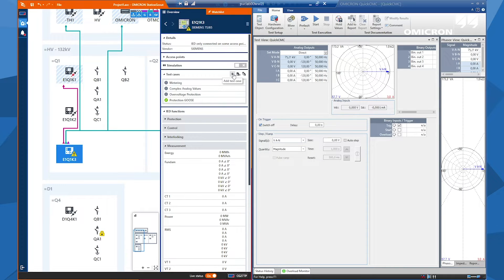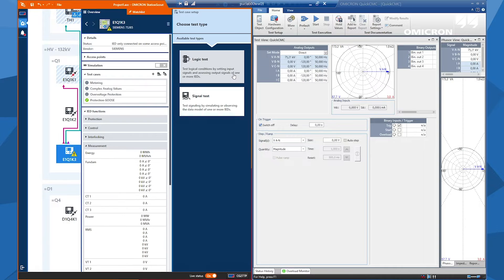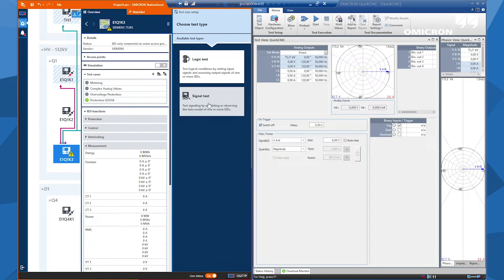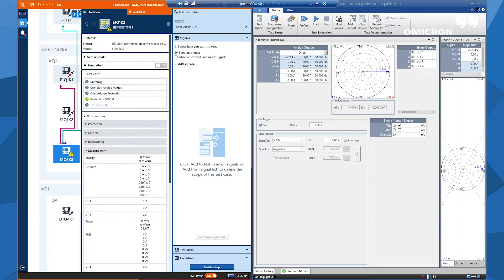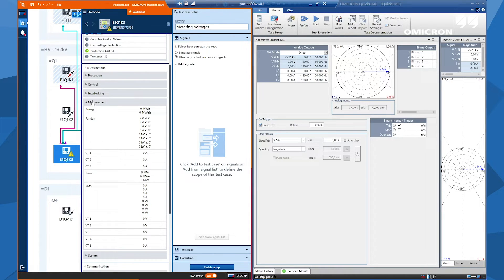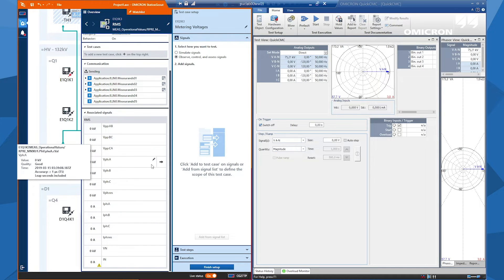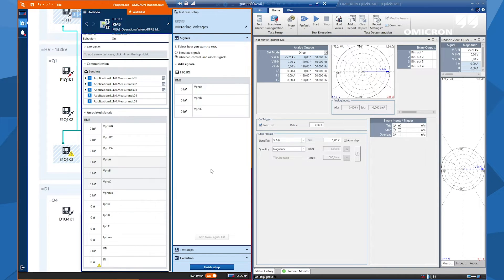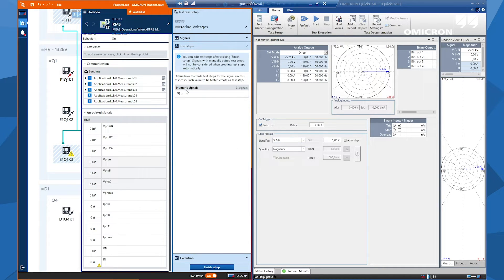I click on the IED and now I click on the test case button. As I want to test the signaling to the SCADA and observe the values, I will now select 'observe values'. I will give a name as 'metering voltages' and now I need to add signals. For adding signals, I expanded the measurement tab of the IED and now I will select some voltages from the RMS values. In the test steps tab, I have the numeric signals only.